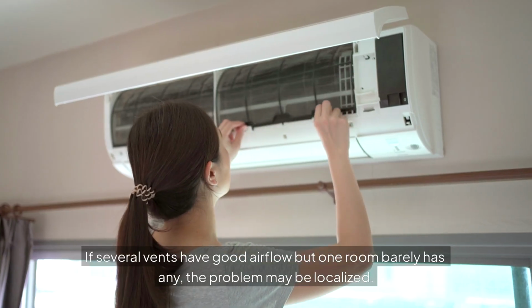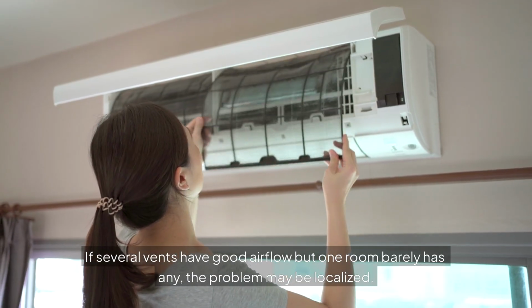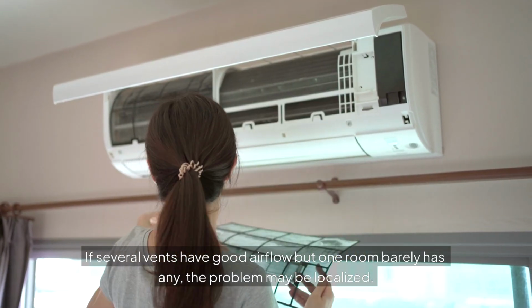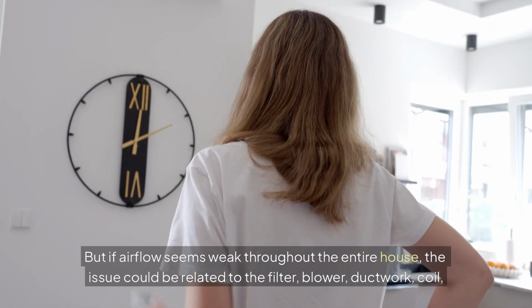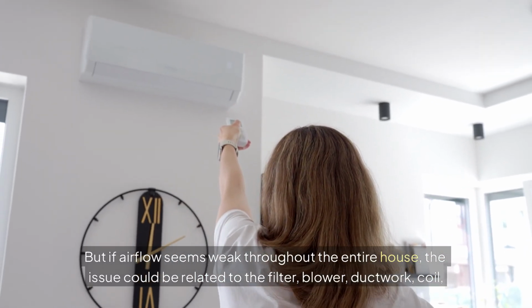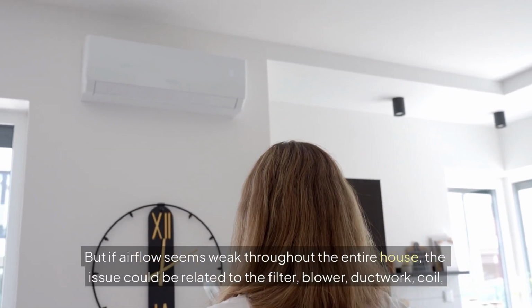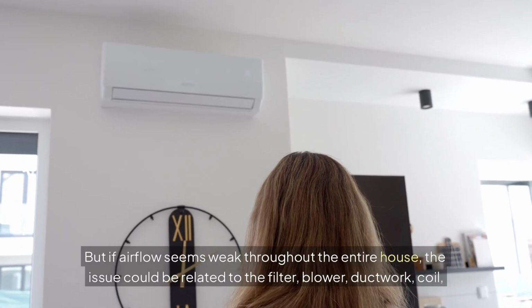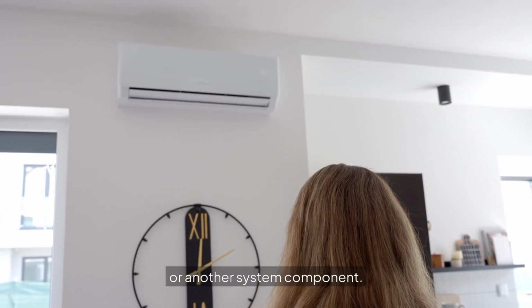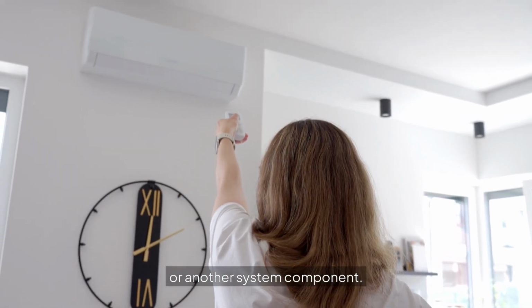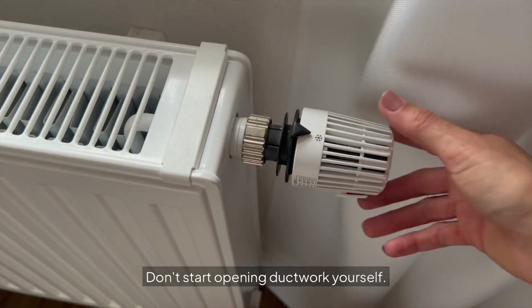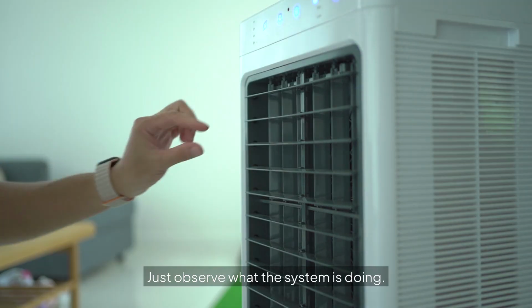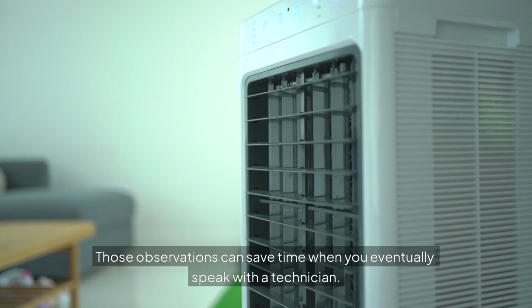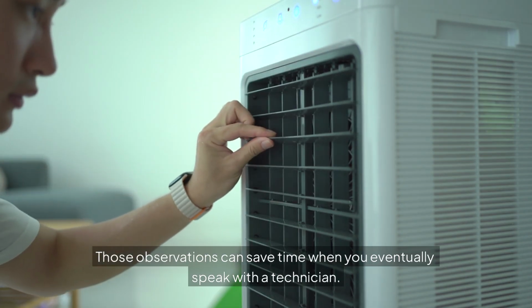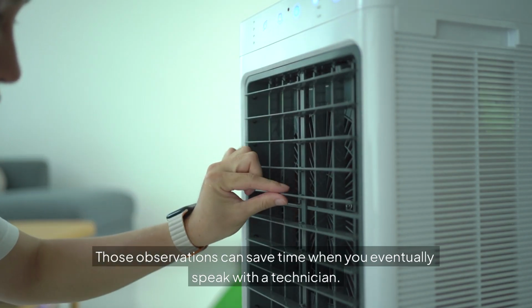If several vents have good airflow but one room barely has any, the problem may be localized. But if airflow seems weak throughout the entire house, the issue could be related to the filter, blower, ductwork, coil, or another system component. Don't start opening ductwork yourself. Just observe what the system is doing. Those observations can save time when you eventually speak with a technician.